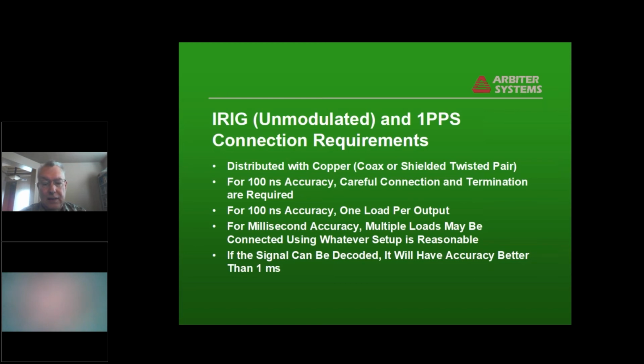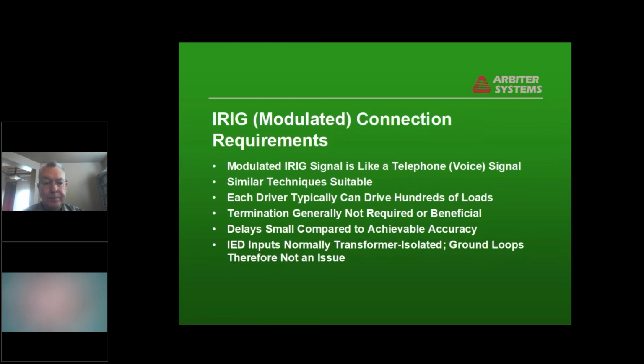But for millisecond accuracy, like for synchronizing event recording equipment, like relays that are just going to generate fault records, and you only have to meet the NERC PRC-018 requirement, multiple loads can be pretty easily connected. And if the signal can be decoded by the IED, it'll be at least the millisecond accuracy that's required for recording. But for a synchrophasor device, for instance, we'd recommend hooking up the clock directly to that load without intervening devices on the line.